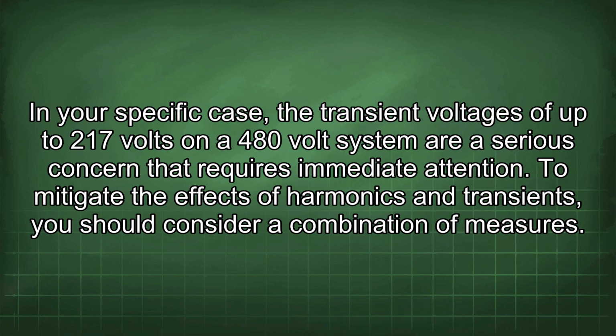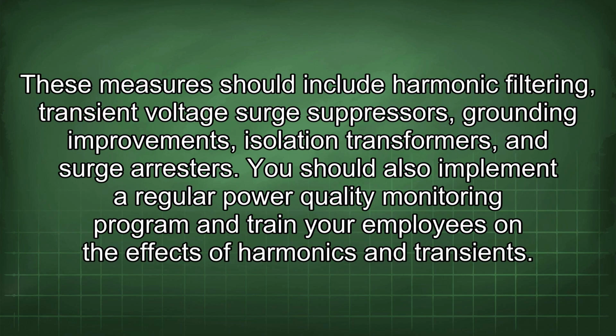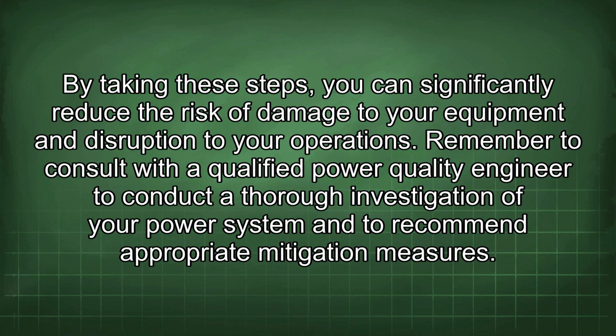To mitigate the effects of harmonics and transients, you should consider a combination of measures. These measures should include harmonic filtering, transient voltage surge suppressors, grounding improvements, isolation transformers, and surge arresters. You should also implement a regular power quality monitoring program and train your employees in the effects of harmonics and transients. By taking these steps, you can significantly reduce the risk of damage to your equipment and disruption to your operations. Remember to consult with a qualified power quality engineer to conduct a thorough investigation of your power system and to recommend appropriate mitigation measures.